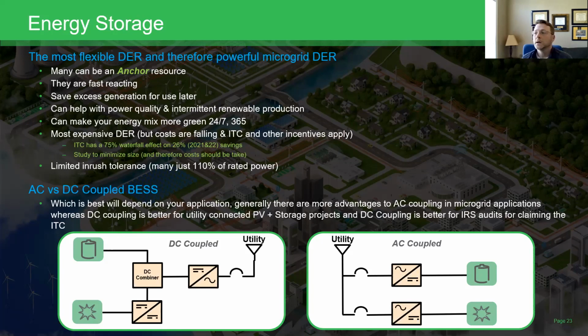And typically, the inverters tied to batteries are rated for around 110% over power for a limited amount of time, like typically around 10 seconds or less. So if you have a 100 kilowatt power rated battery, it might be able to provide 110 kilowatts momentarily to help manage inrush. But if your inrush is greater than that, you're going to have a problem.